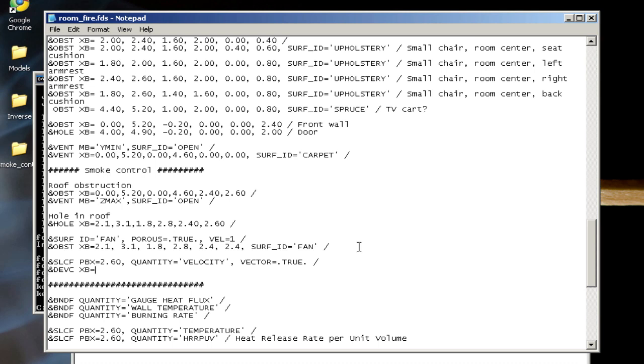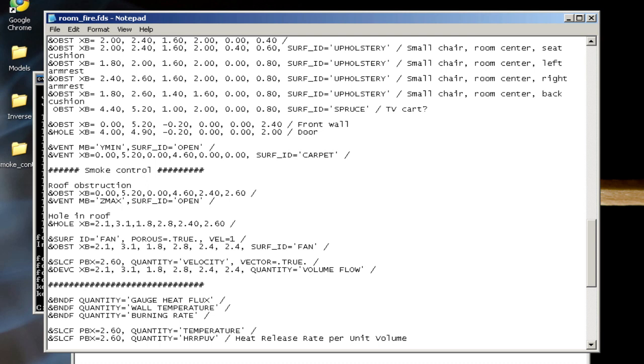It's going to be a plane: 2.1, 3.1, 1.8, 2.8, and on the z dimension 2.4 to 2.4. I'm going to set this to quantity equals volume flow. This is going to give me a nice integrated quantity over that area and show me the volumetric flow rate in cubic meters per second flowing through that area. It's a really nice way to check to make sure that my fan is behaving as it should and giving me the volume flow rate that I want.